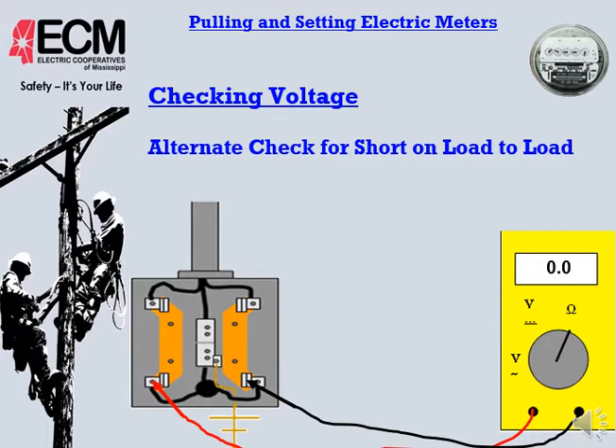In this particular setting, when you check phase to phase on the load side, we want to make sure our meter's in ohms position. I had a situation where in an apartment complex, I was checking voltage and got to this step and found the two conductors tied together, where if I had set the meter, it would have been a dead short, phase to phase short right in my face. So when we get to this position, we want to make sure it's in ohms position to check for continuity. We're making sure those conductors are not tied together.